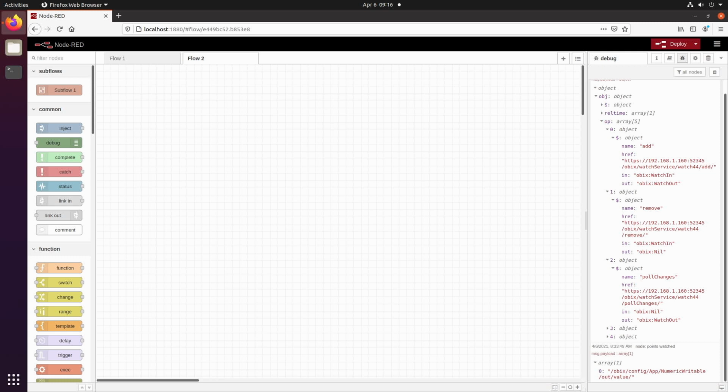Now what we're going to talk about is a special operation in oBIX that's known as the watch. And what is the watch for? Well, if you've got a lot of data points that you would like to pull out of Niagara4 into NodeRed via oBIX, and you want those data points to update live, and you have a number of them, more than one, any number, 5, 10, 20 of them, 2,000 of them, the tool that you want to reach for is a watch.